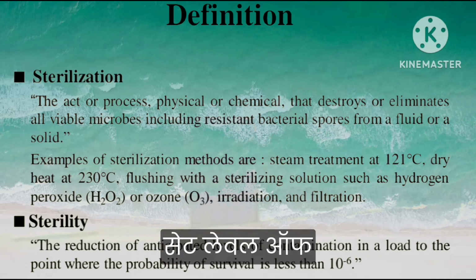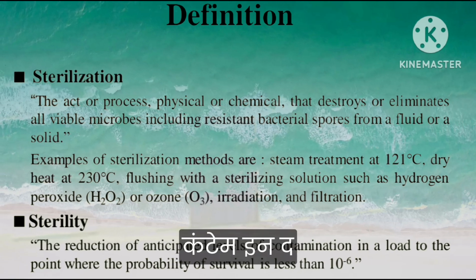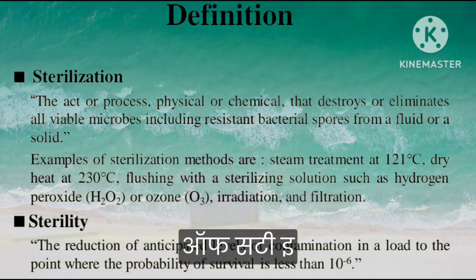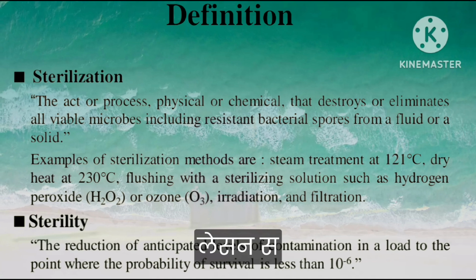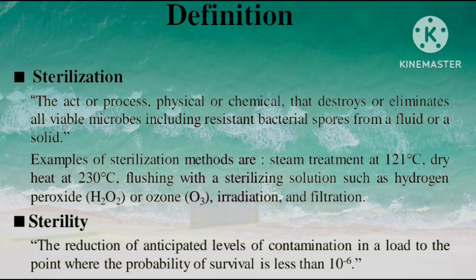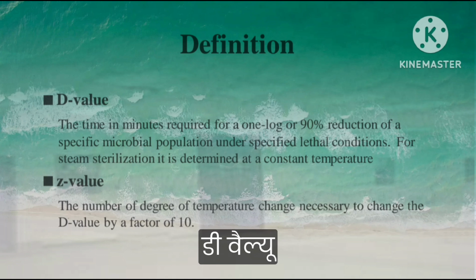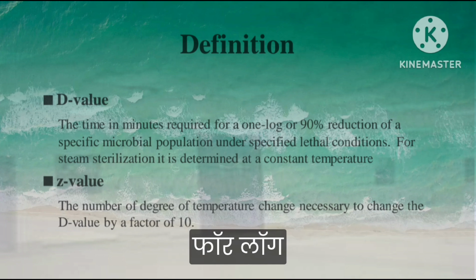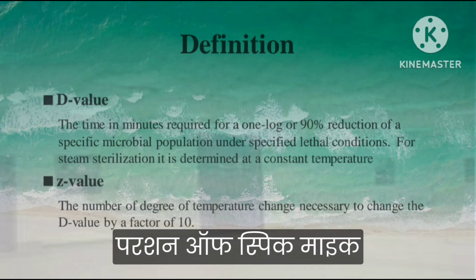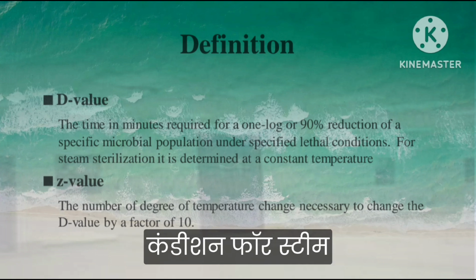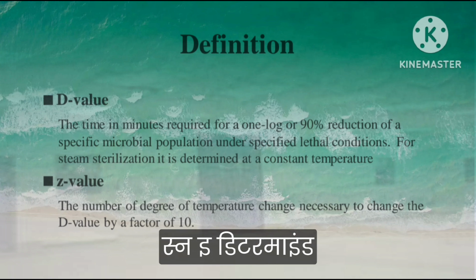Sterility: the reduction of the level of contamination in the load to the point where the probability of non-sterility is less than 10 to the minus 6. D value: the time in minutes required for a one log reduction, or 90% reduction, of a specific microbe population under specific lethal conditions. For steam sterilization it is determined at constant temperature.